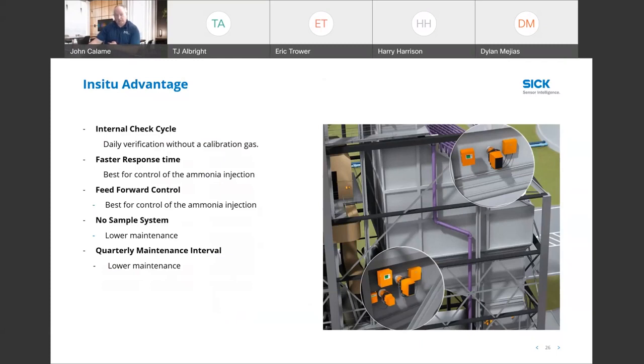You can do your own calculations in your head on how much money that would save you there. And also, we all know that the analyzer is guilty until proven innocent. So if you have to challenge the analyzer, or if there's a challenge from operations and it's not working, you can physically hit it, maybe a digital signal, send it to the analyzer, and then you have positive indication of performance. So that's huge when you have a question about the analyzer operations, questions the reading. You can initiate this verification cycle for testing as well as to meet the daily verifications via the EPA.